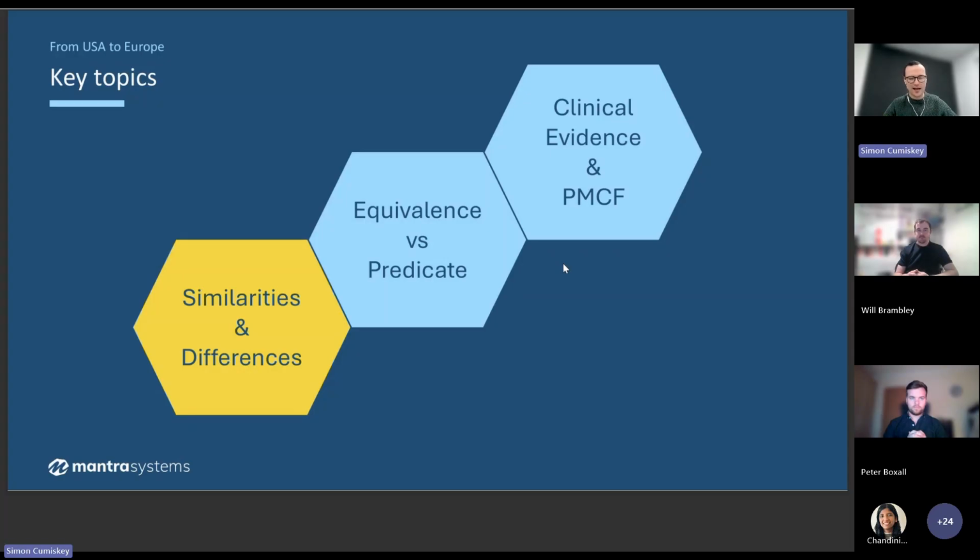At an administrative level, they're quite different, really. The FDA in the US is the regulator of the medical device space. So with that, they've got very well-defined approval timelines, costs, and they publish a lot of guidance that explains how you can apply the FDA regulations to your medical device.